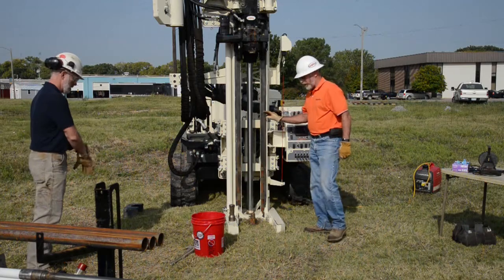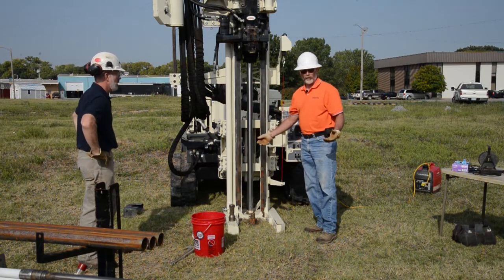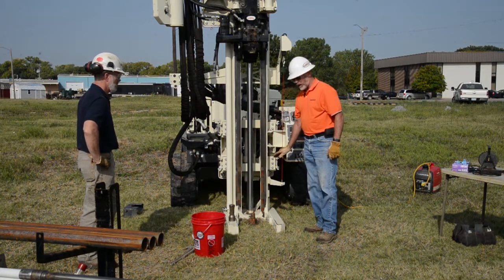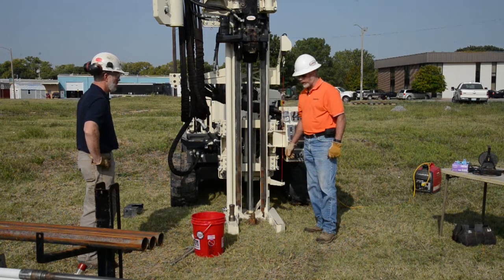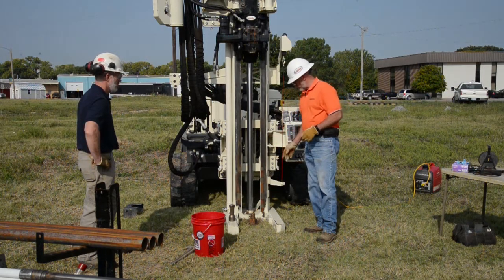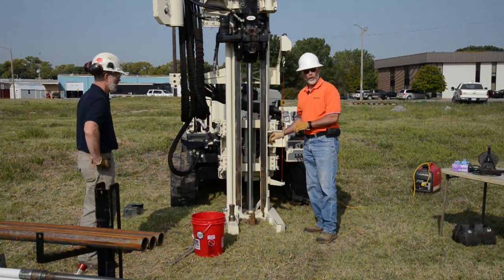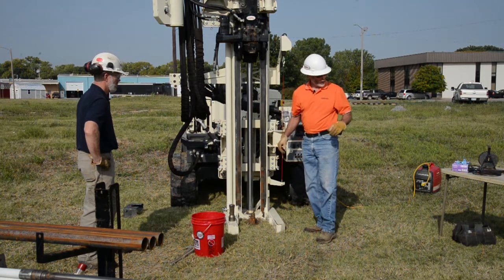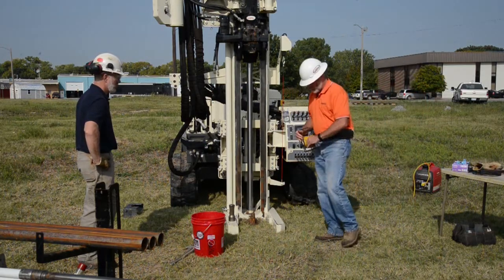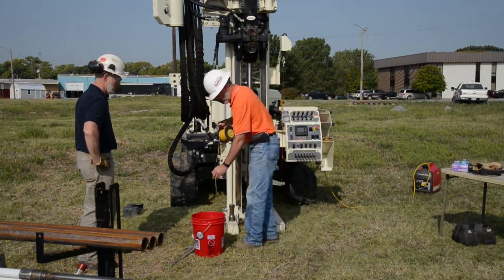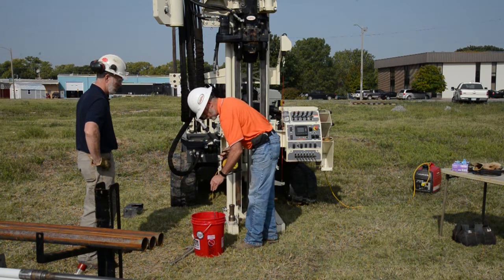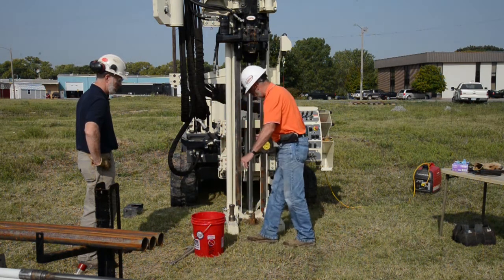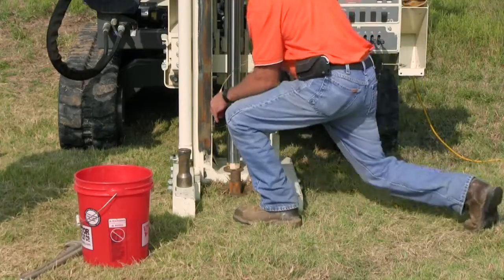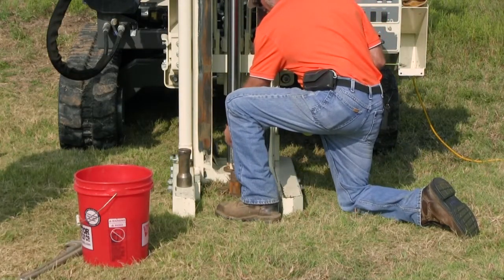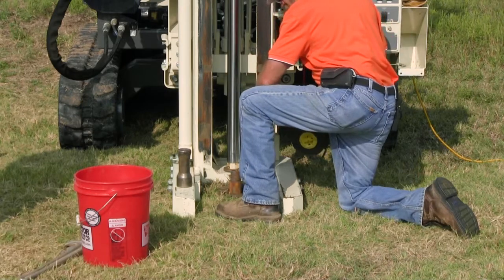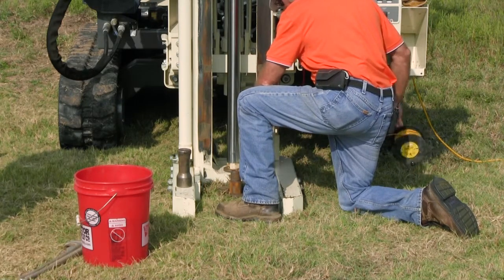Okay, so now we have 8 rods in the ground. We're using 5-foot rods. So with the stick up, we have 40 feet of rods in the ground. We're going to check our total depths and see if there's any fluid or anything in the hole with our little water level indicator. So this is our old water level indicator here. And probably as you can hear, it beeps when we hit the water. So we're going to lower down, check our depth, and make sure we have 40 feet of rod in the ground, and check for any fluid in the rods.